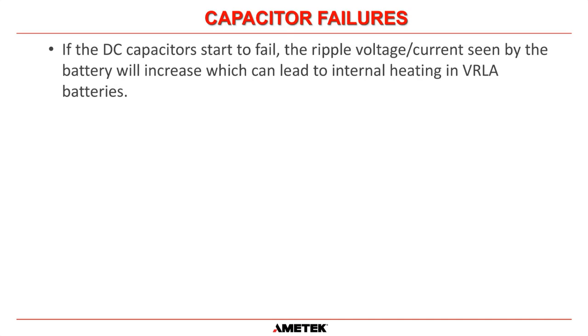If the DC capacitors start to fail, the ripple voltage current seen by the battery will increase, which can lead to internal heating in VRLA batteries, which could then lead to thermal runaway. So it can even cause microcycling of wet cell batteries as well. So part of your maintenance regime should be checking the ripple going to your batteries. And if you see that increasing year over year, then it could be an indication that the capacitors inside your UPS or charger could be failing.